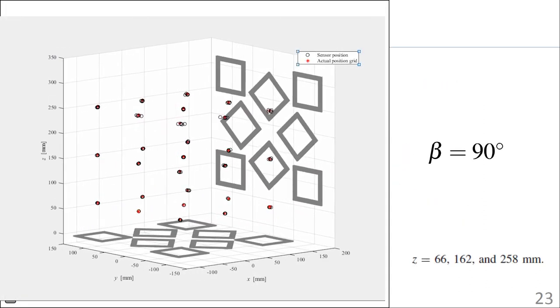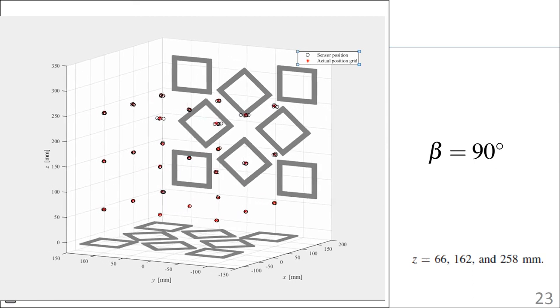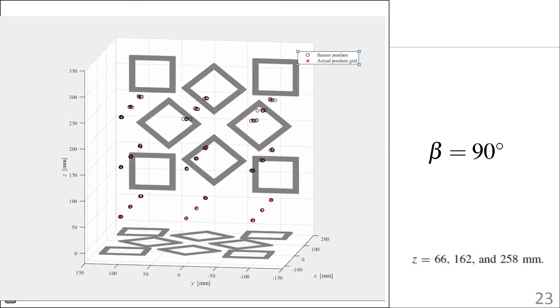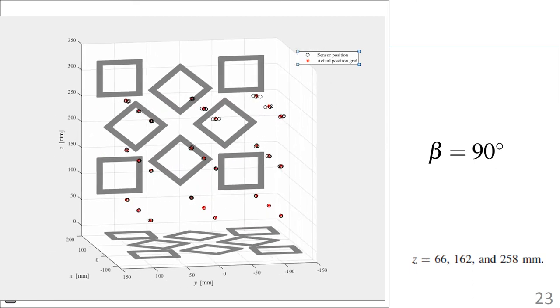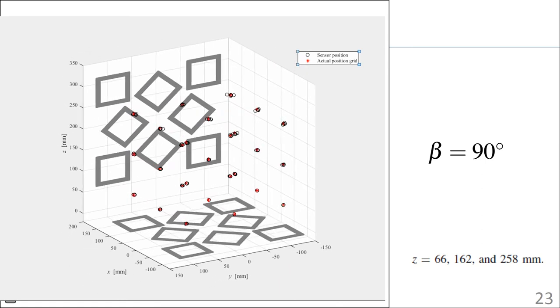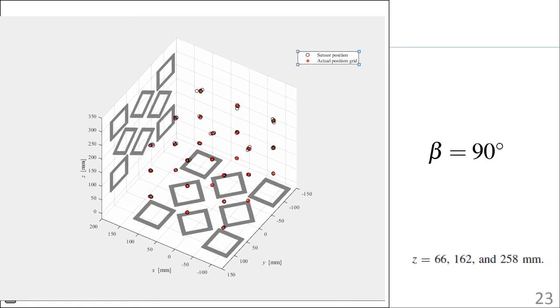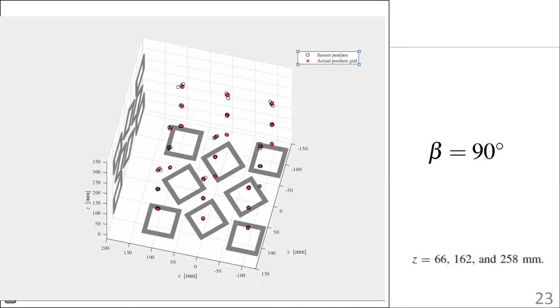This animation shows the results of the fiducial registration accuracy measurement for a tilt angle of 90 degrees. The reference grid locations are shown in red and reported sensor positions are shown in black. Three grid heights were used for taking these measurements.